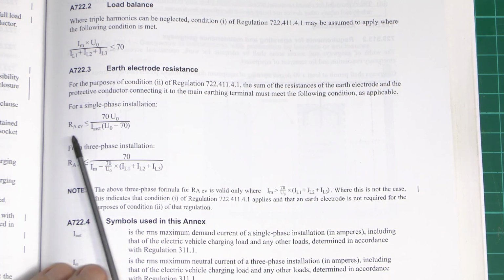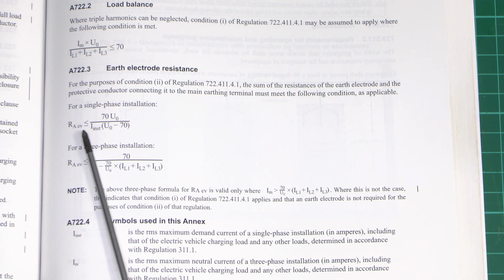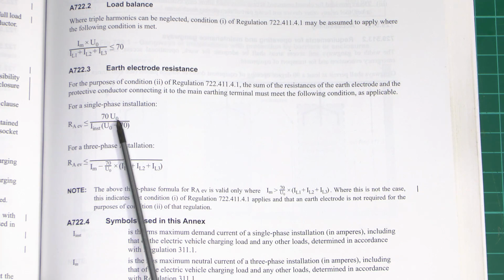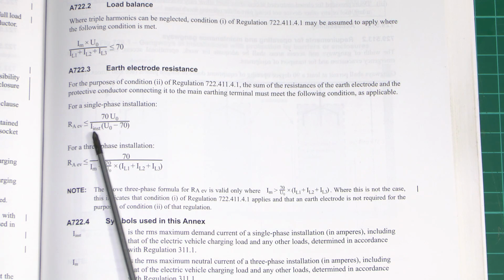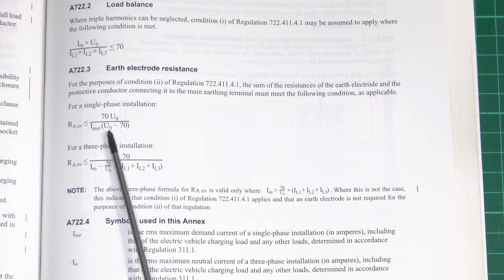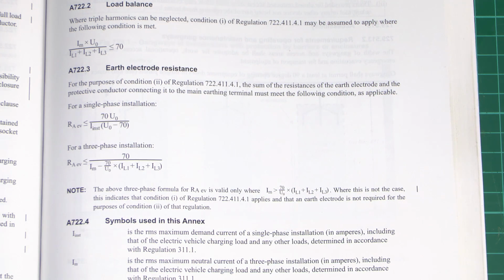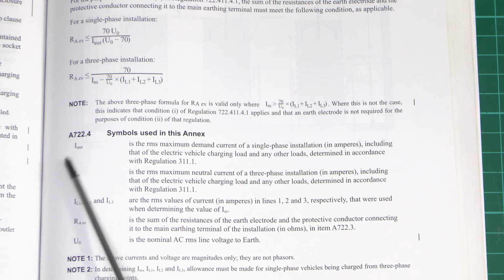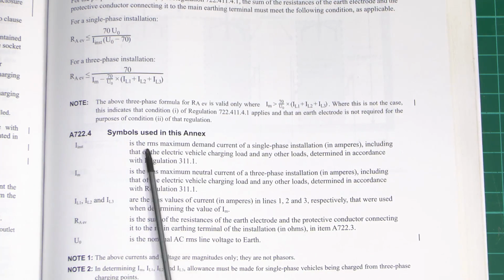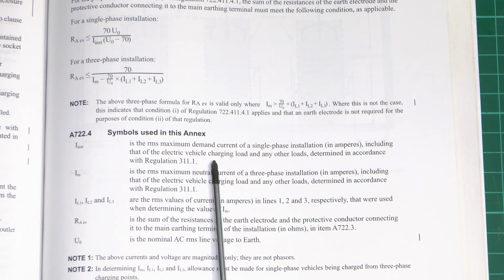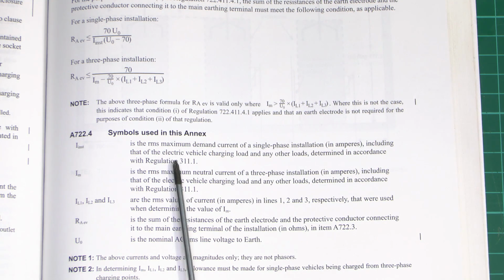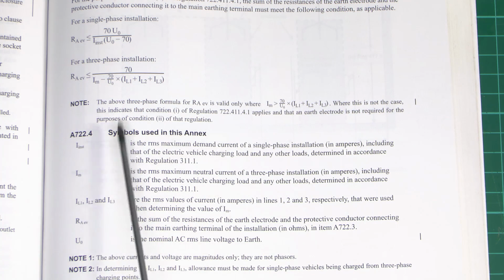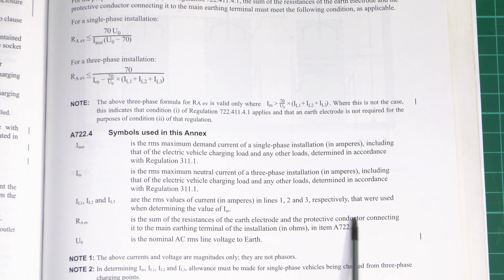So we've got RA is smaller than or equal to this formula here, which is basically 70 times the voltage, and this is the installation current, and then it's multiplied by, again, the voltage minus 70, so it's one divided by the other. Now we can see the definitions here. The I inst is the maximum demand current of the installation, including that of the electric vehicle charging load and any other loads. So basically it's the total load of whatever the building or installation is. U0 is the nominal AC RMS line voltage to earth, so it's going to be your 230 in most cases. And RA, of course, is the sum of the resistances of the electrode and the protective conductor.